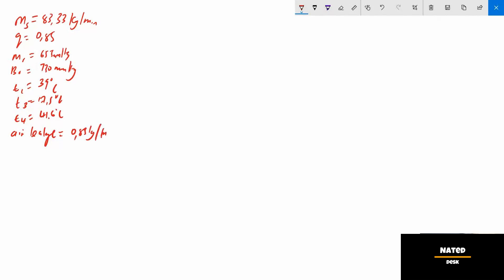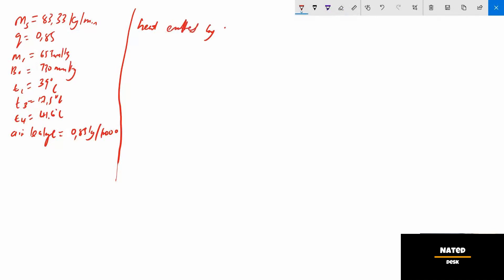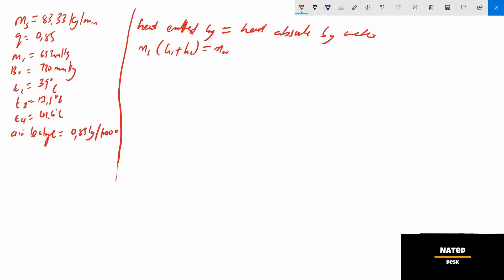Let me divide the screen for more space. The first question asks to calculate the mass of cooling water, mw. To calculate mw we use the heat balance formula: heat emitted by the steam equals heat absorbed by the water. That is: ms × (h1 + hc) = mw × cpw × (t4 − t3). Before calculating mw, we first need to calculate h1.